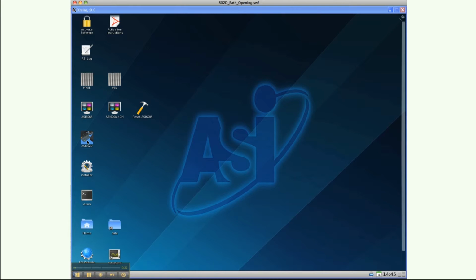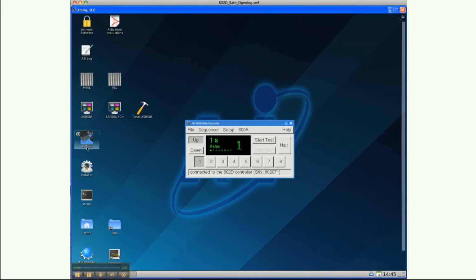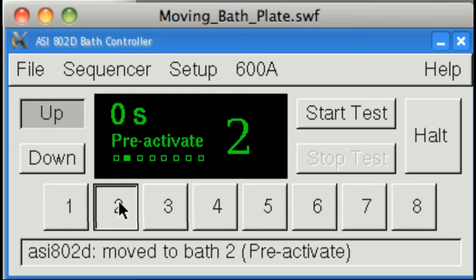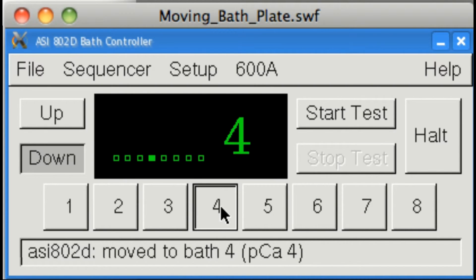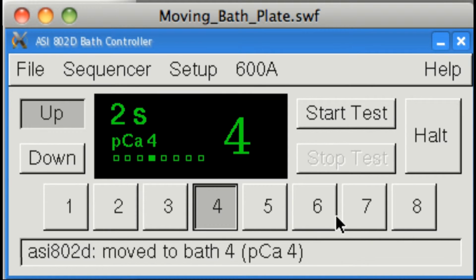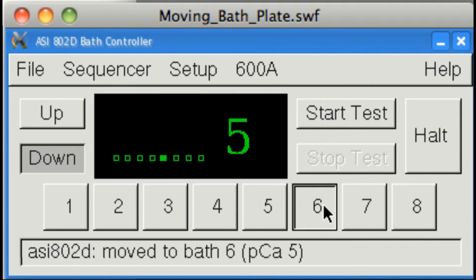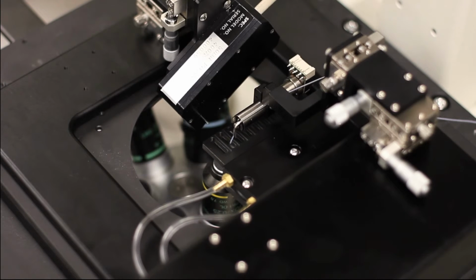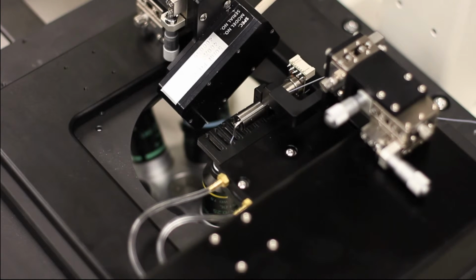With the 802D unit turned on, you can now start the 802D bath control software. The software should automatically determine what bath chamber number the apparatus is currently set to. Take note of this and press the button to move to an adjacent bath. Proceed to move through each bath one by one and ensure that the bath plate moves and does not interfere with the microscope stage.